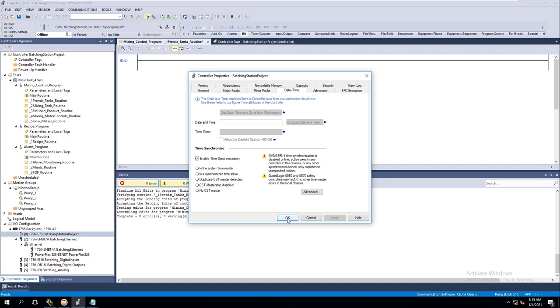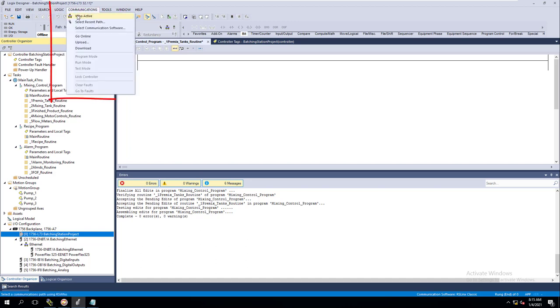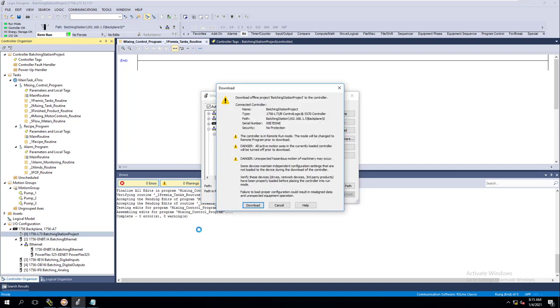So, to do that properly, time synchronization needs to be turned on if you are running a motion group inside of your processor and you are controlling the servos of that processor, right? So, at that point, we'll click OK. We'll go up to Communications, go to Who Active, and we're going to download one more time. And then we should not have any kind of errors in our processor.